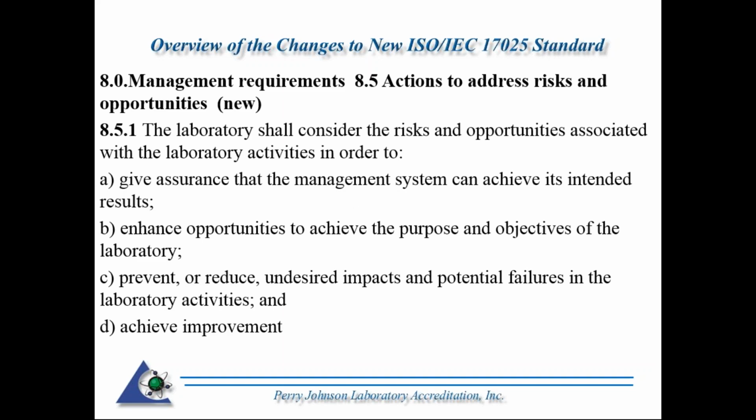So as we get under management requirement 8.5, we have a new section here, actions to address risk and opportunities. And we have the word shall there. The laboratory shall consider the risk and opportunities associated with the laboratory activities in order to give assurance that the management system can achieve its intended results, enhance opportunities to achieve the purpose and objectives of the laboratory, prevent or reduce undesired impact and potential failures in the laboratory activities, and achieve improvement.